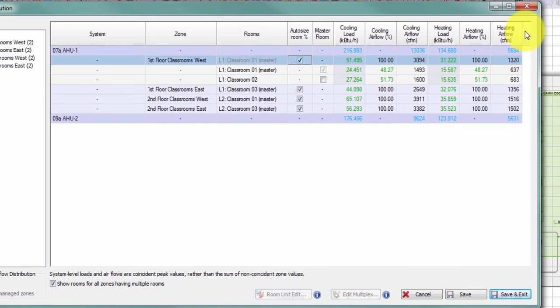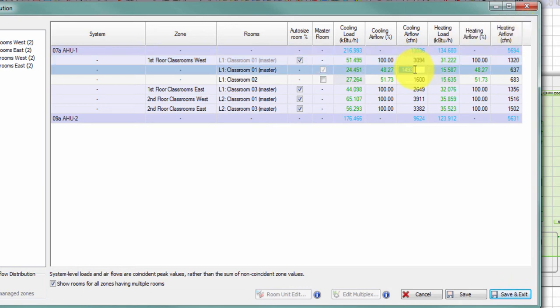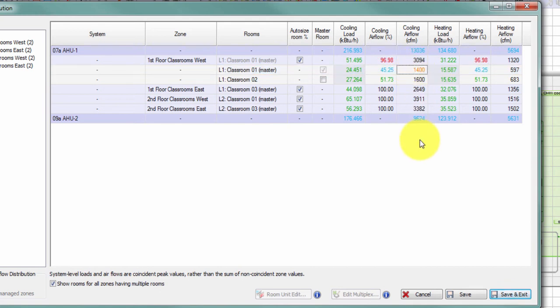To change the distribution of airflow to spaces within a zone, I can double-click and edit the numbers. For example, if I don't want 1493 CFM delivered to classroom 1, I can change it to 1400. That value now appears in orange, indicating a local edit as described earlier.